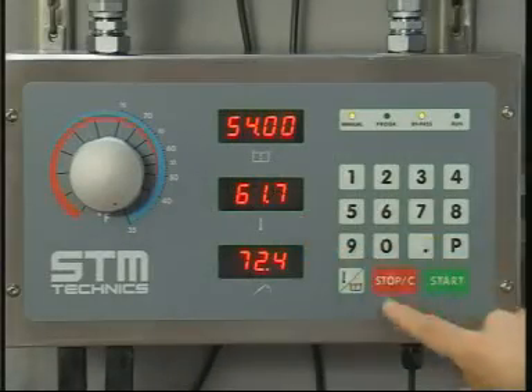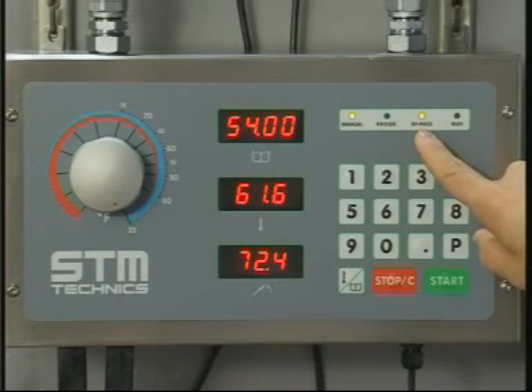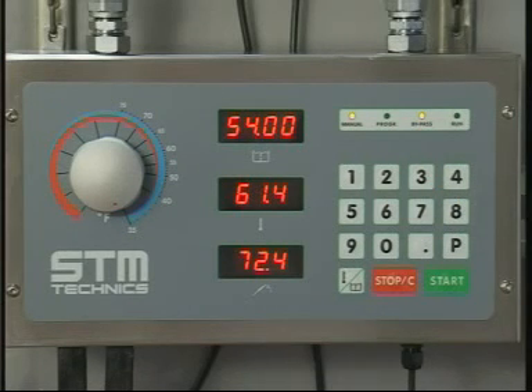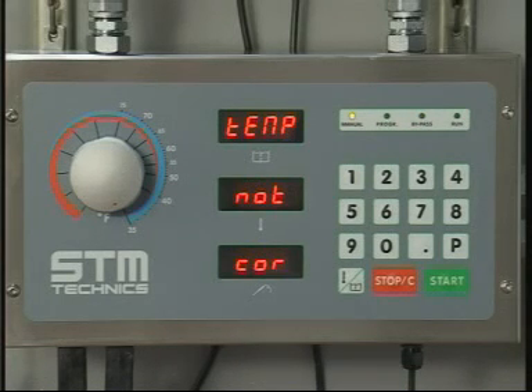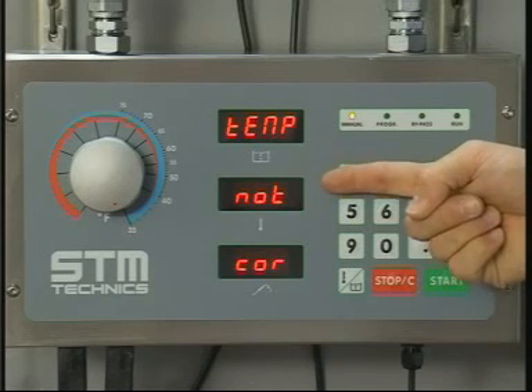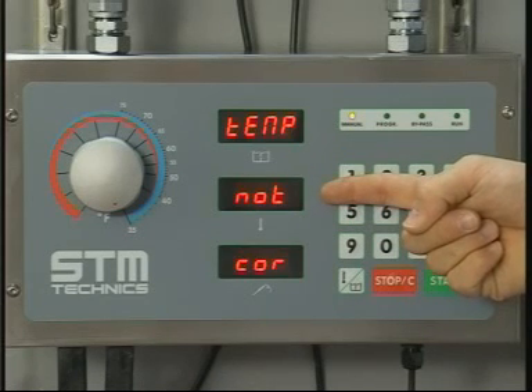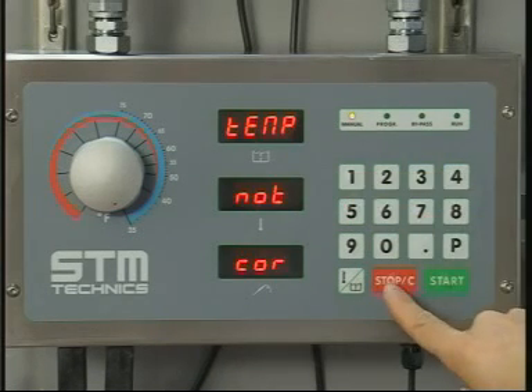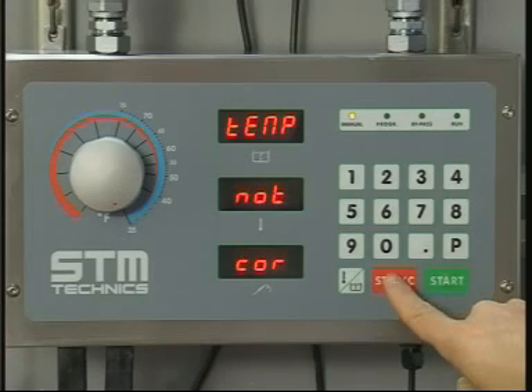Unreachable temperature error. If during a delivery the machine remains in bypass for a long period and the temperature programmed cannot be reached despite moving the regulation knob, temp not cor appears on the display and the delivery stops with the buzzer sound. Press stop twice to block the alarm.